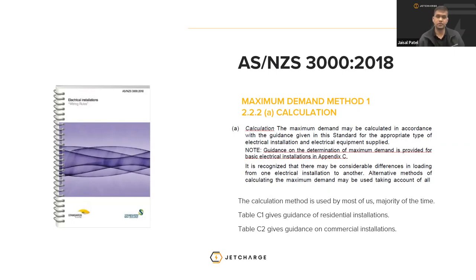The calculation method is when we calculate the max demand. It may be calculated in accordance with the guidance given in the standard for the appropriate type of electrical installation supplied. And for EV chargers, they have two tables. Table C1, which is a guidance on residential installations, and table C2, which gives us guidance on commercial installations. Next slide.